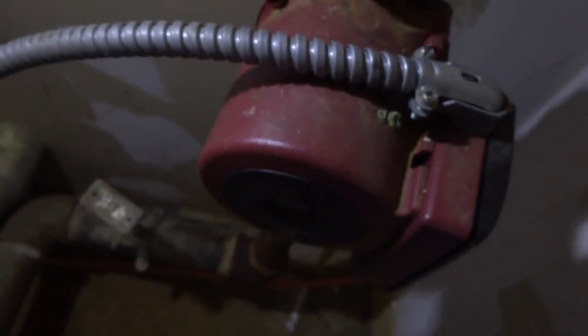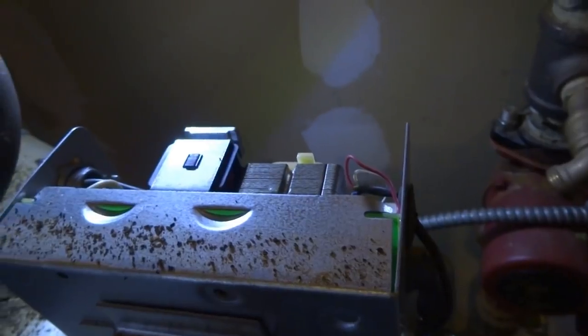Behind this boiler here, I can barely fit behind here. It's calling. You can see it's out. It smells burnt, but there's no power going to the circulator. So I gotta change this control. Not gonna be easy back here because there's really not a lot of room. It's calling. Limit. I gotta see if I got a control. I gotta change this.